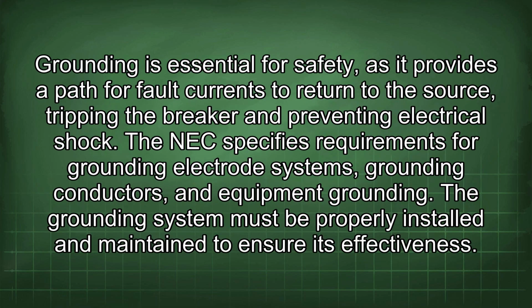Grounding is essential for safety, as it provides a path for fault currents to return to the source, tripping the breaker and preventing electrical shock. The NEC specifies requirements for grounding electrode systems, grounding conductors, and equipment grounding. The grounding system must be properly installed and maintained to ensure its effectiveness.